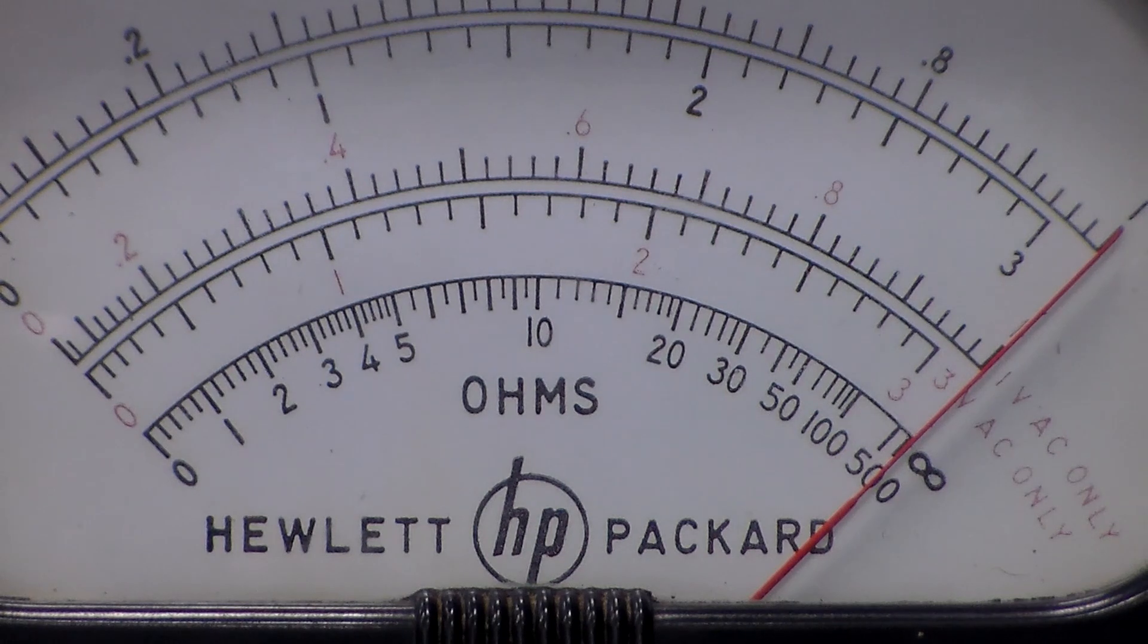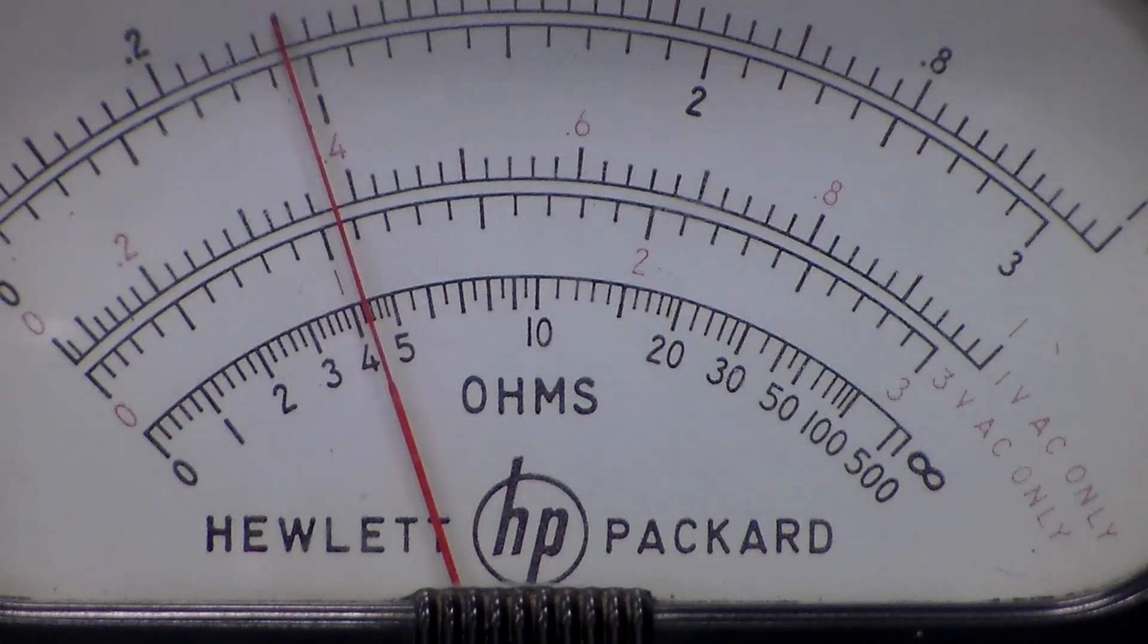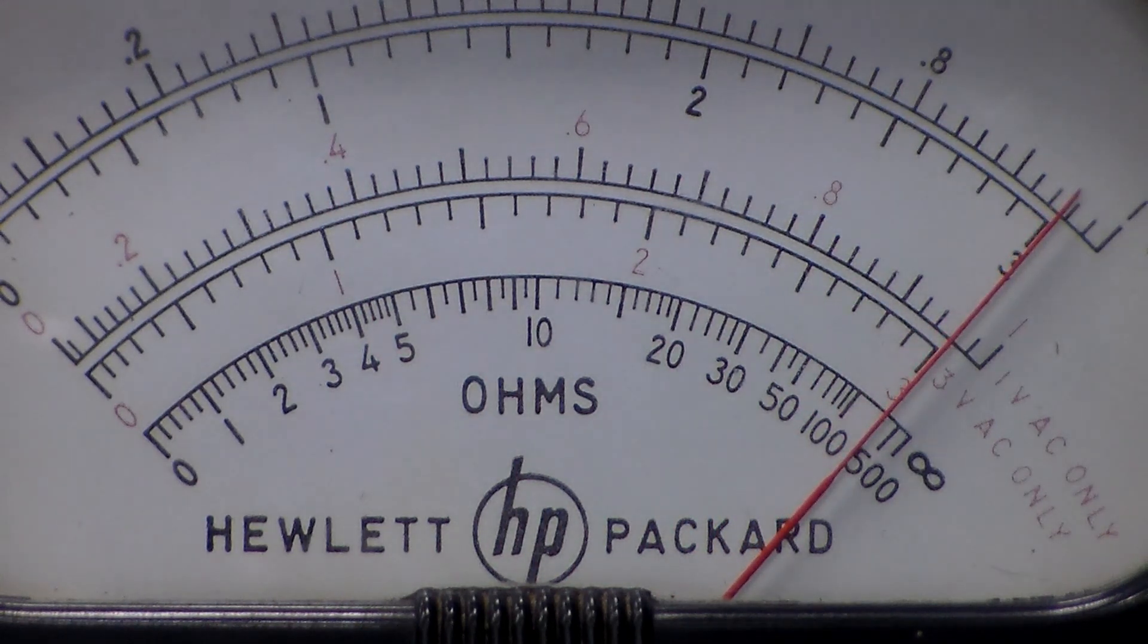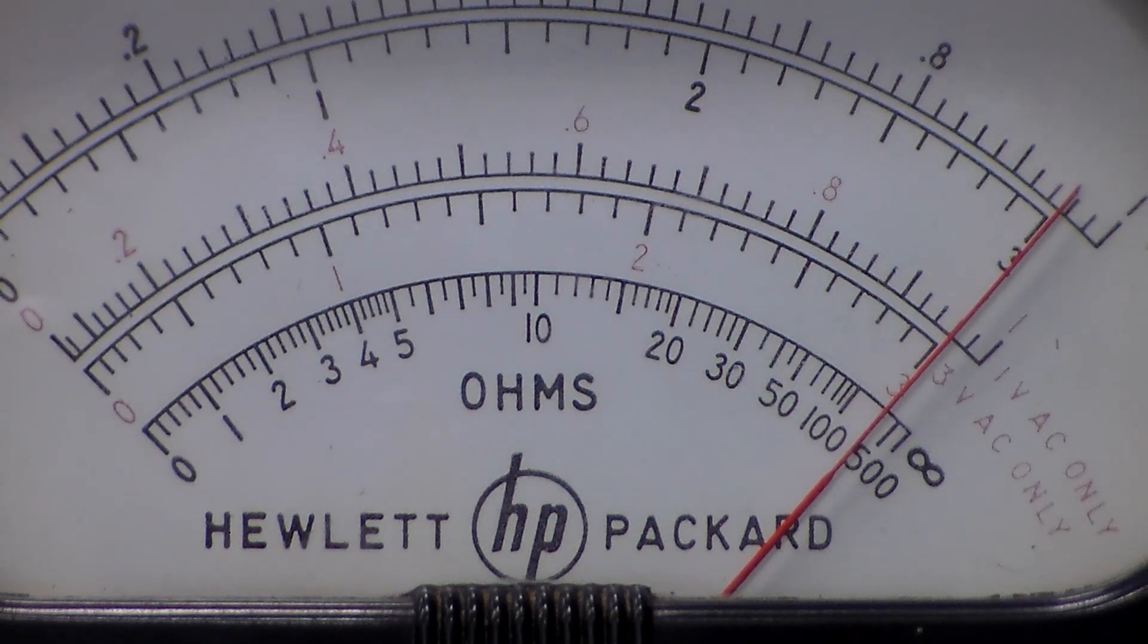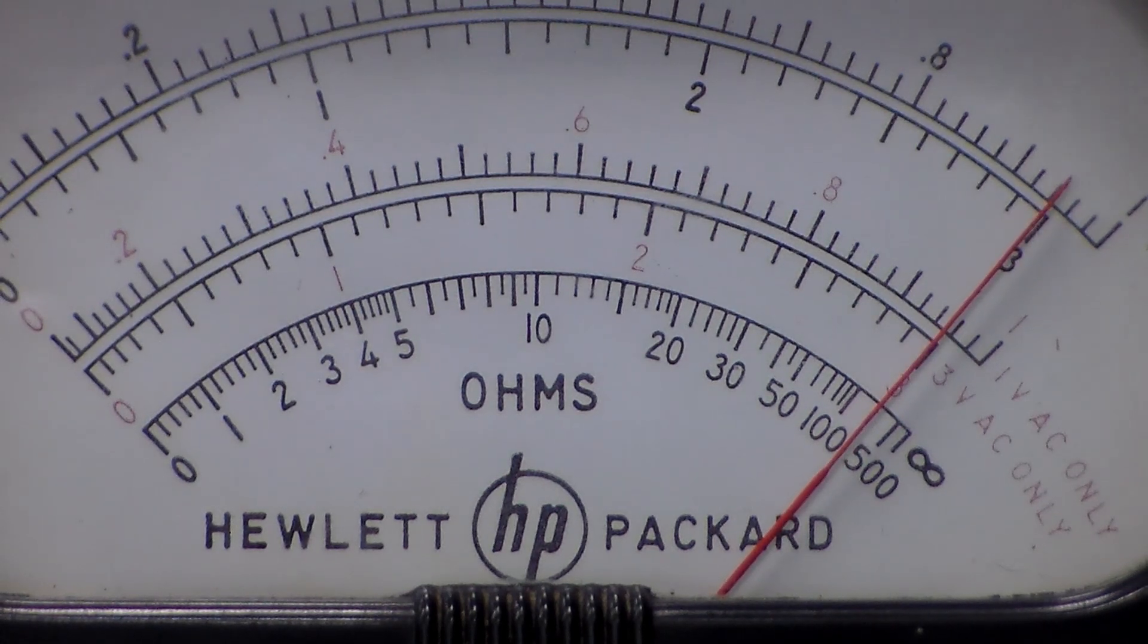1 volt here now is on this lower scale, this is the 3 volt AC range, and it's reading a little bit high. What we need to do first is set that to 3 volts. It is reading a fraction high there. We need to adjust the 3 volt gain setting pot, which is R39. We just bring that down a touch.